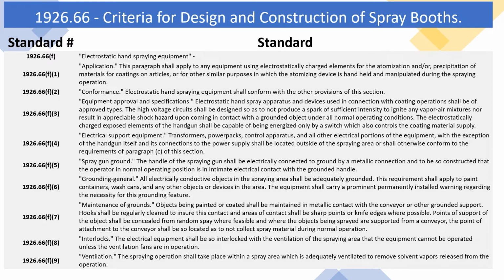1926.66 F6 Grounding general. All electrically conductive objects in the spraying area shall be adequately grounded. This requirement shall apply to paint containers, wash cans, and any other objects or devices in the area. The equipment shall carry a prominent permanently installed warning regarding the necessity for this grounding feature. 1926.66 F7 Maintenance of grounds. Objects being painted or coated shall be maintained in metallic contact with the conveyor or other grounded support. Hooks shall be regularly cleaned to ensure this contact, and areas of contact shall be sharp points or knife edges where possible. Points of support of the object shall be concealed from random spray where feasible and where the objects being sprayed are supported from a conveyor. The point of attachment to the conveyor shall be so located as to not collect spray material during normal operation.